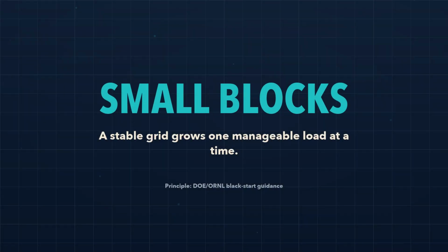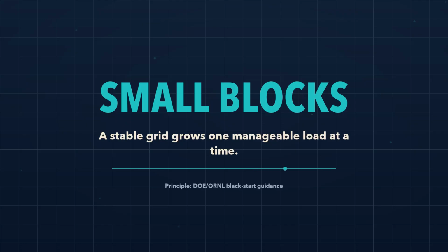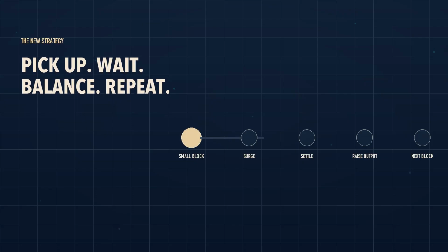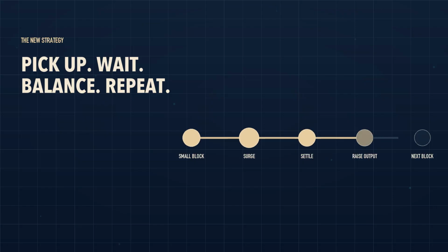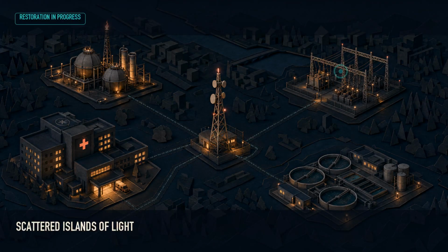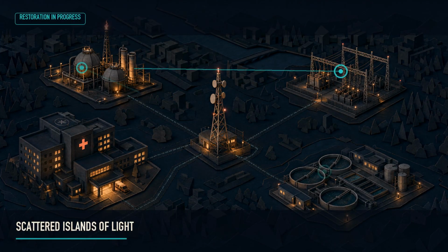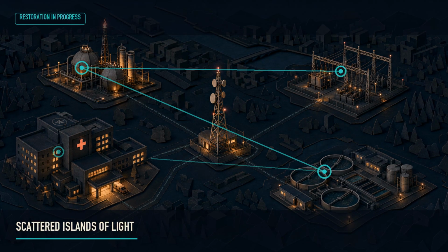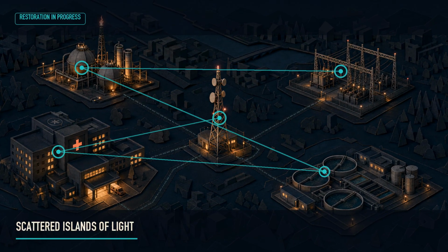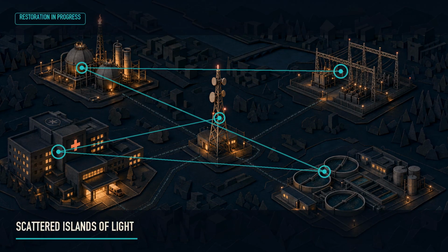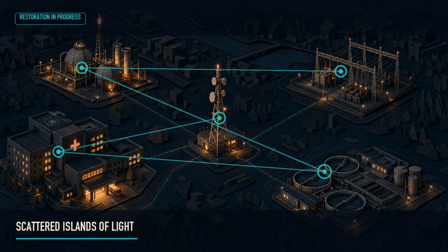That is the trick television blackouts hide. A city does not return in one heroic reveal. Restoration happens in electrical bites small enough for the living island to swallow. The new strategy is slower and much better. Split the feeder, pick up one block, wait for the restart surge to settle, raise generation, check voltage and frequency, then repeat. Lights return as scattered islands. Water pumps here, a hospital district there, communications near the river, traffic control along one corridor. The result is less cinematic than a skyline and far more believable.